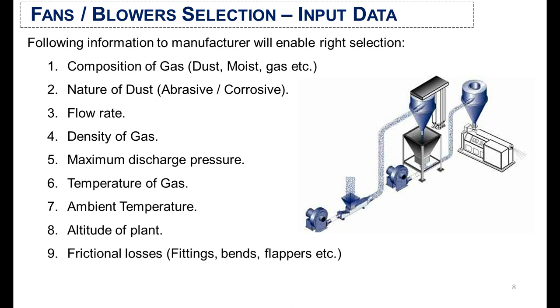Fourth is the density of the gas. Fifth is the maximum discharge pressure required at the downstream of the flow. Sixth is the temperature of the gas. Seventh is the ambient temperature at which the blower will be installed. Eighth is the altitude of the plant — the height at which the blower will be installed — and accordingly the suction and discharge piping network will be routed to that elevation. Ninth is the friction losses at the suction and discharge ducts in the form of fittings, bends, and flappers.